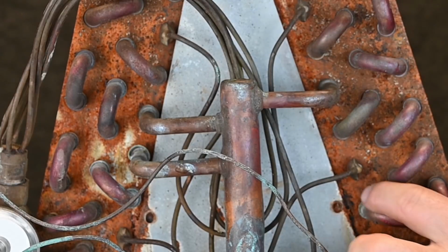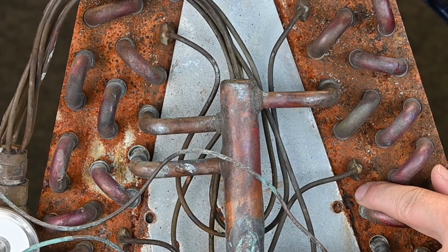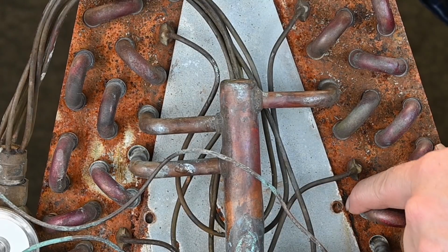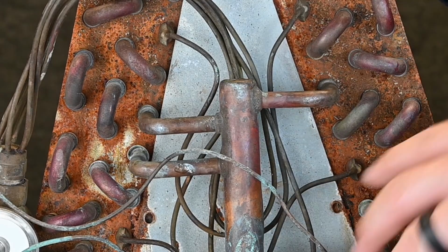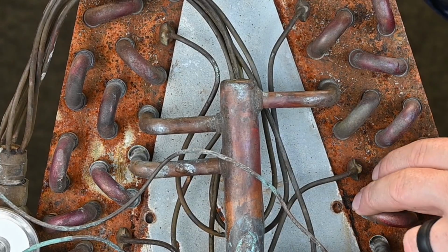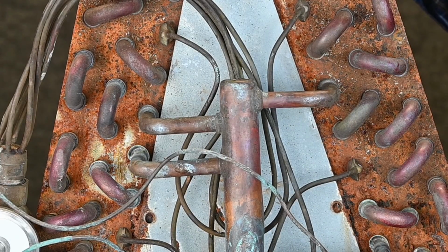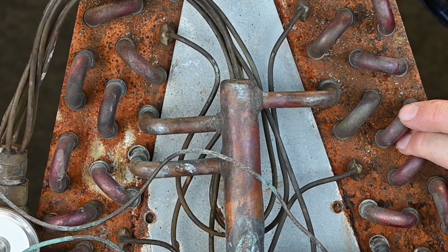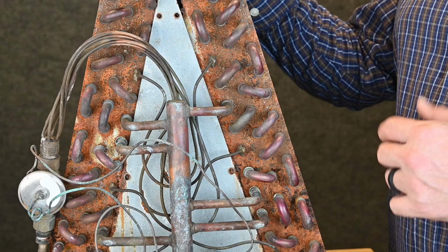Just because it's rusted doesn't mean it's going to leak, but I do want to note that on the customer's invoice. I want to say, sir or ma'am, we did find some signs of aging. It's rusting. It's not leaking right now, but I just do want to inform you of that. Doesn't mean we have to jump and replace this. It's just giving us signs and letting us know it's older. We don't want to rush and jump and replace this whole entire evaporator coil just because there's some rust. However, we do want to note it so they're not surprised if there is an issue.